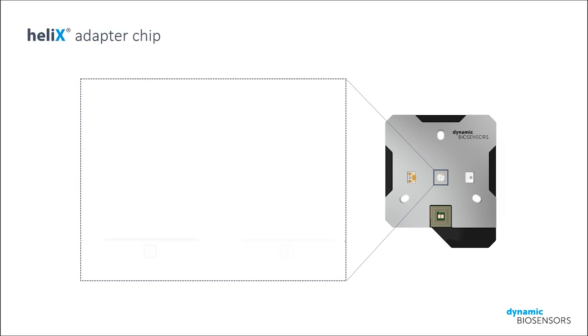The Helix adapter chip features a versatile linker system to immobilize and exchange molecules on the detection spot. It consists of three building blocks, which are all made up of DNA. The anchor is a 48-mer DNA strand that is covalently connected to the gold microelectrodes of the chip via thiol chemistry. The chip already comes pre-modified with anchors which remain on the surface at all times. The two detection spots are modified with different unique anchor sequences, so they can be individually modified later by a technique called DNA-encoded addressing.